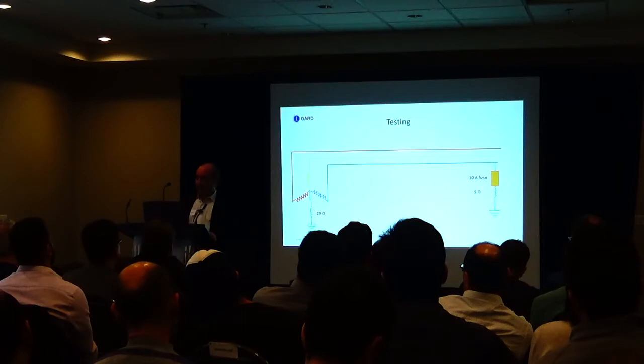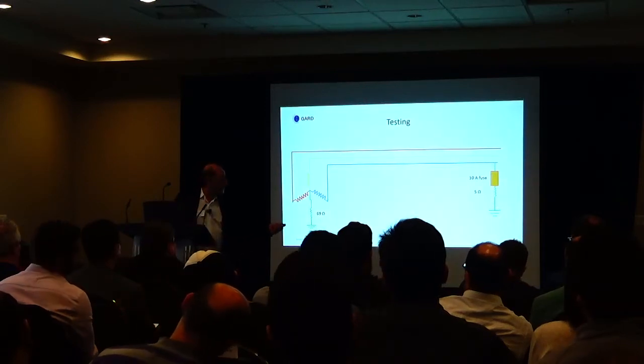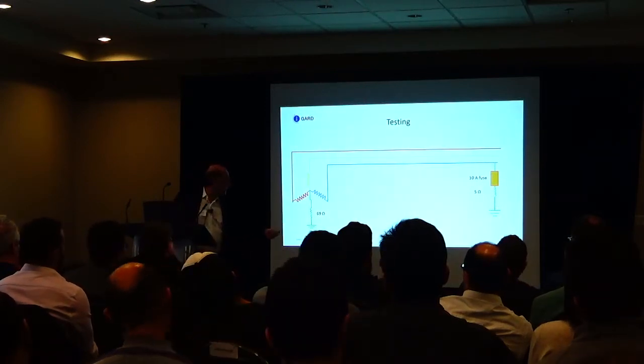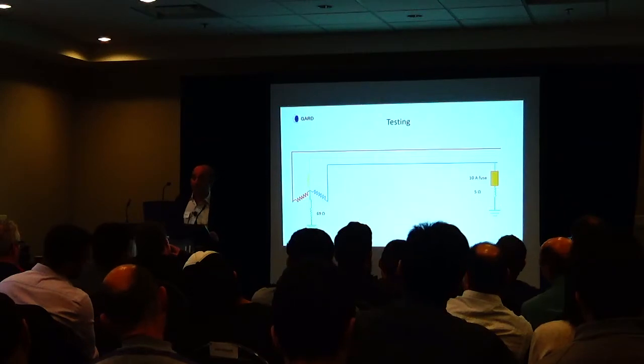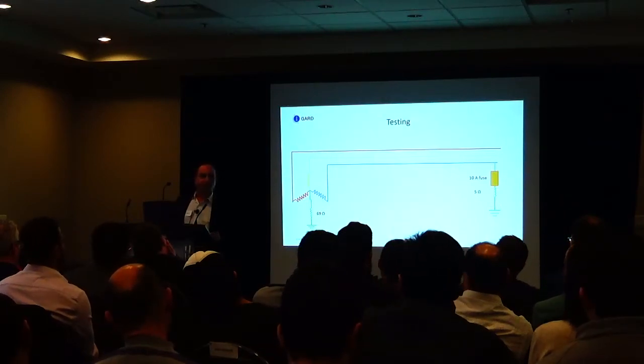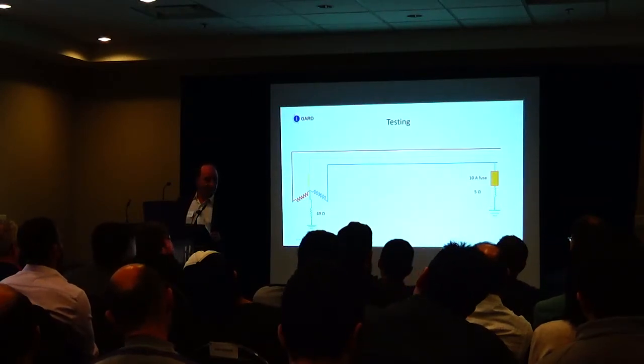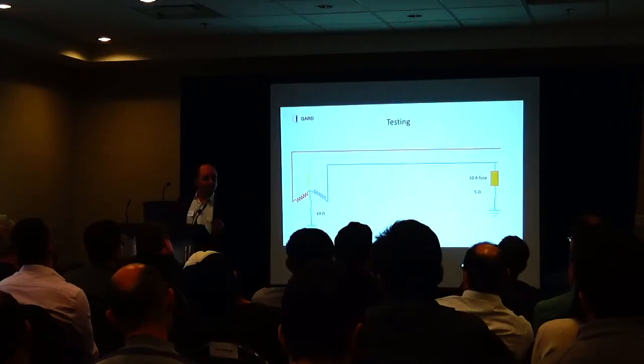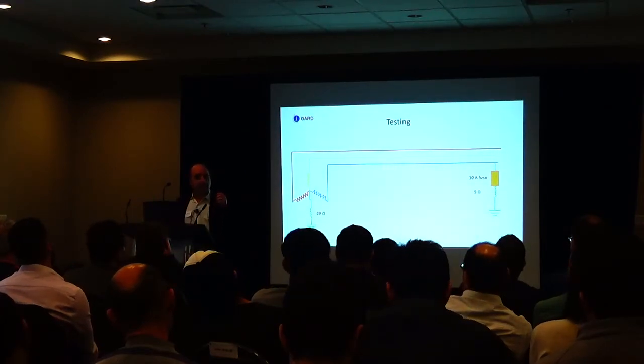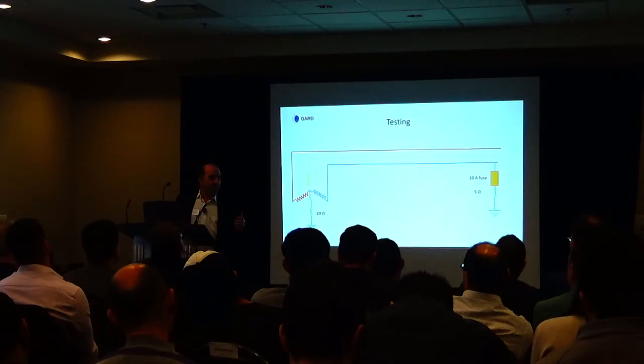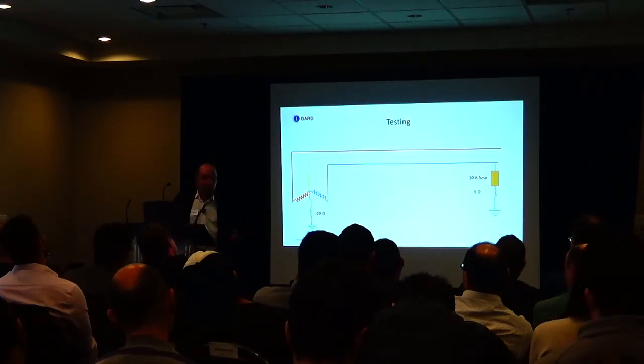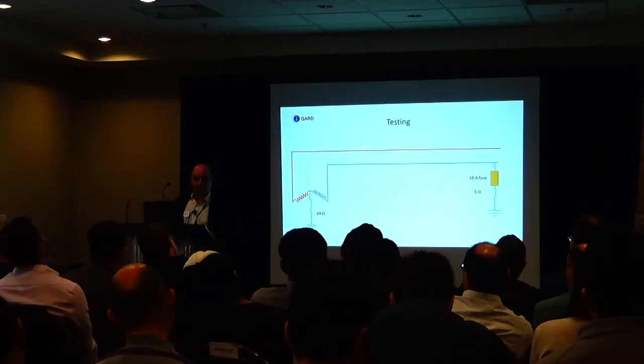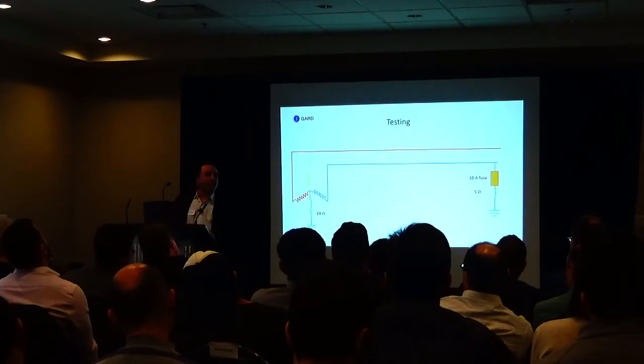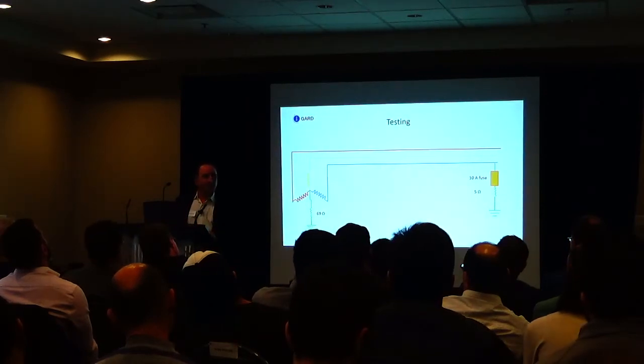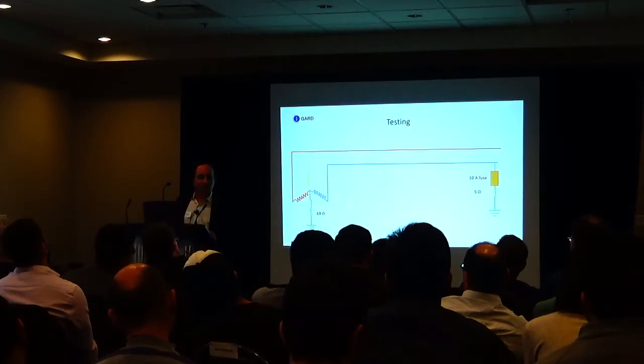Now what happens? If we have a fault here, and we have 14 ohms in the path, we're going to get just under 5 amps. If we get under 5 amps, we're good. That means the load is compatible with the resistance ground in the system, and it's truly a resistance ground in the system. If we get 70 amps, and we blow the fuse, what happens? That means we have a solidly grounded system.